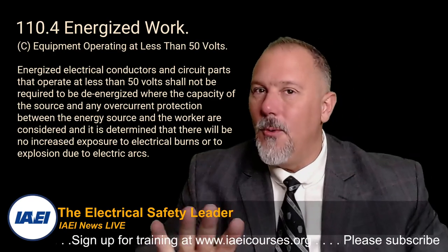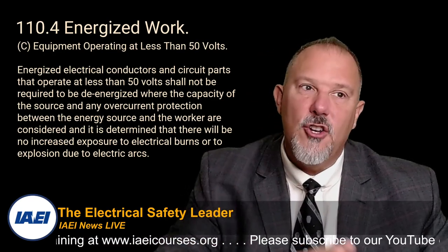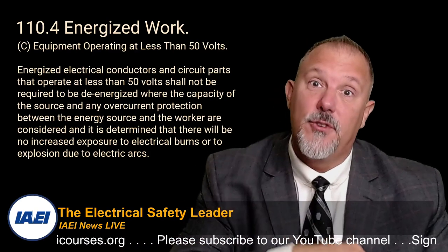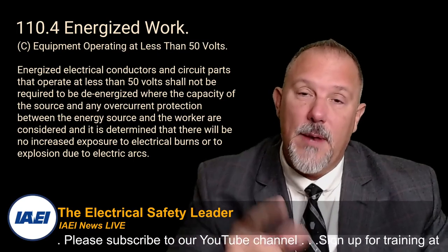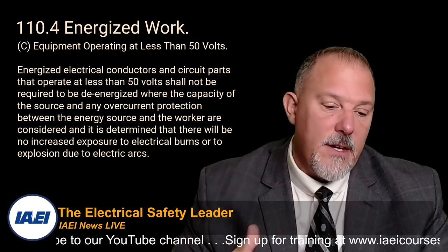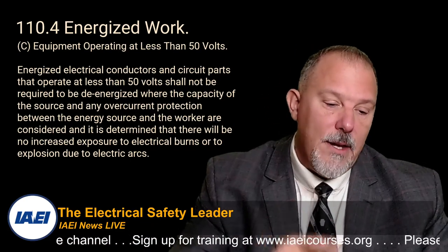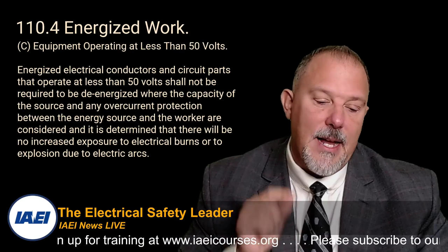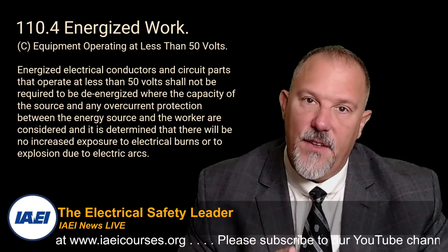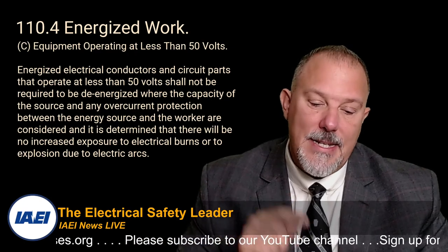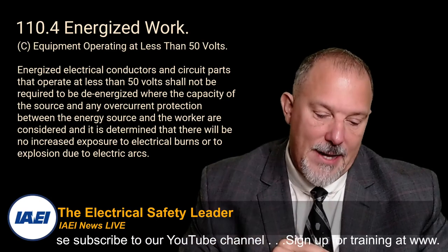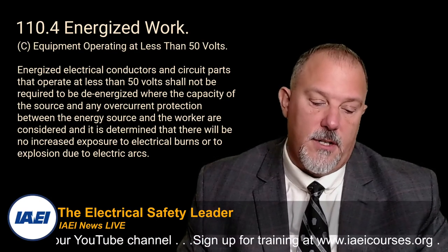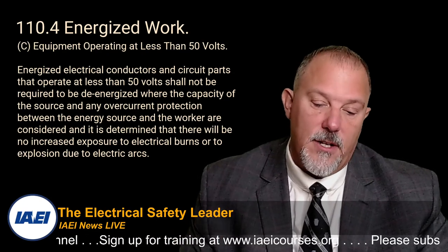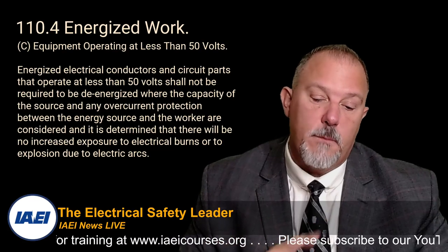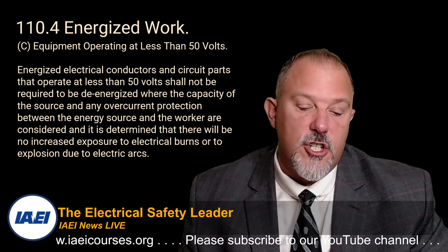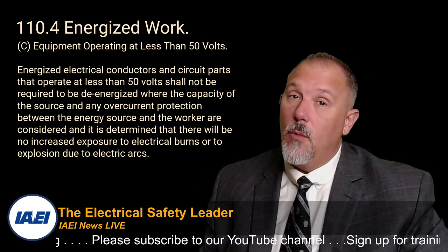And then 110.4 says, all right, hold on. We understand that sometimes you might not be able to establish an electrically safe work condition. And these are those times that we deem when you don't have to. I call it, and it's not a defined term, justified energized work, right? And 110.4C tells us energized electrical conductors and circuit parts that operate at less than 50 volts shall not be required to be de-energized where the capacity of the source and any overcurrent protection between the energy source and the worker are considered, and it is determined that there will be no increased exposure to electrical burns or to explosion due to electrical arcs.